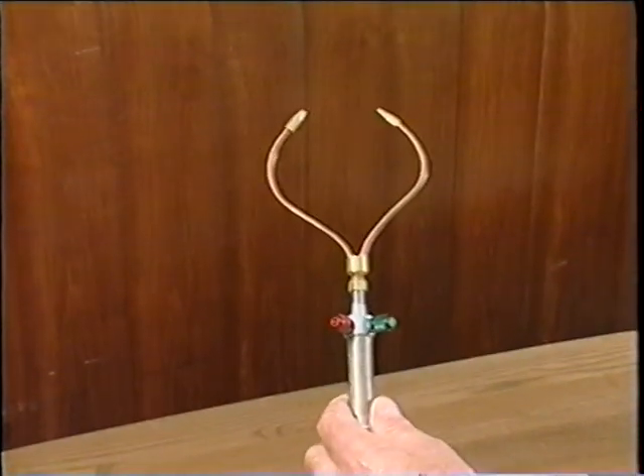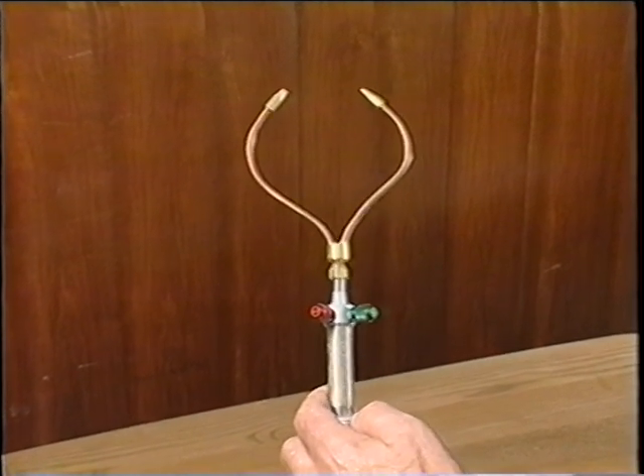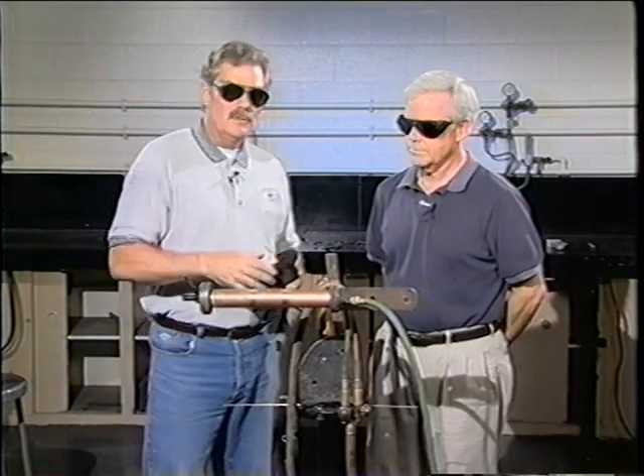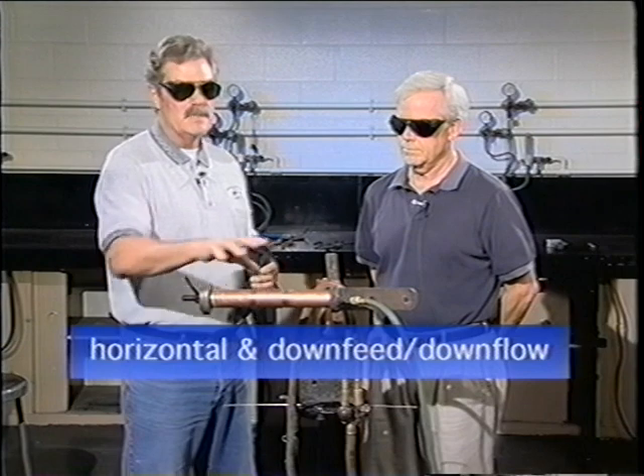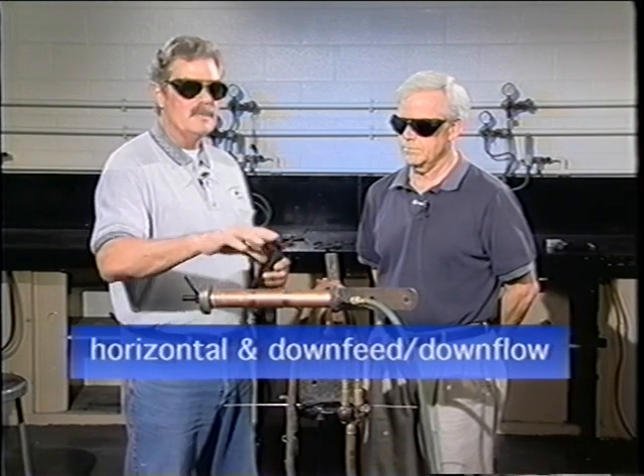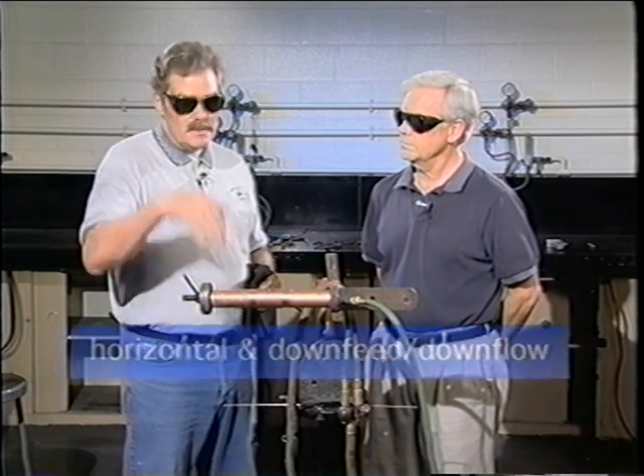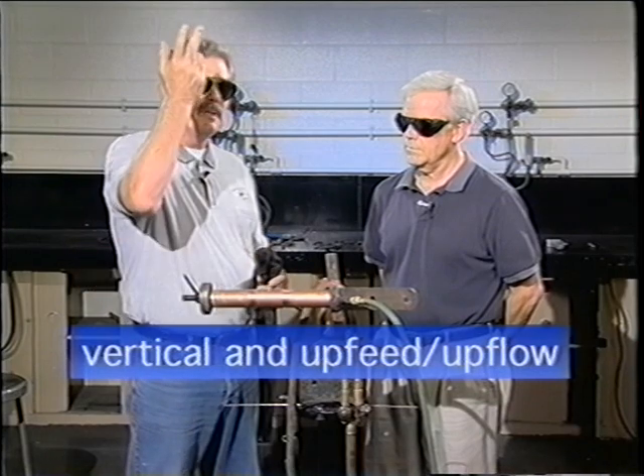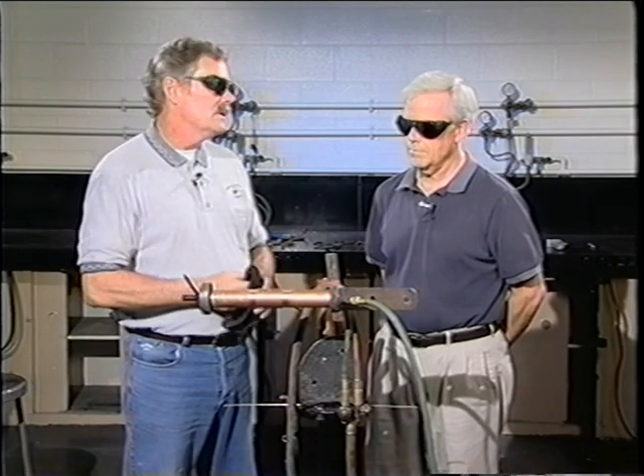This is another oxygen-acetylene torch with a dual tip that also works well in a confined space or tight area where you want to control where the heat is put on the joint. The horizontal joint position, when you've accomplished two joints, qualifies you for horizontal joints and down-feed (downhill). The vertical joint — where I'll make two up-feed joints — qualifies you for uphill or up-feed joints and horizontal. So that covers all the positions in which you may find yourself brazing pipe in a medical gas installation.